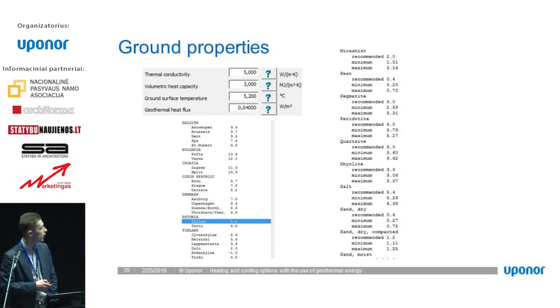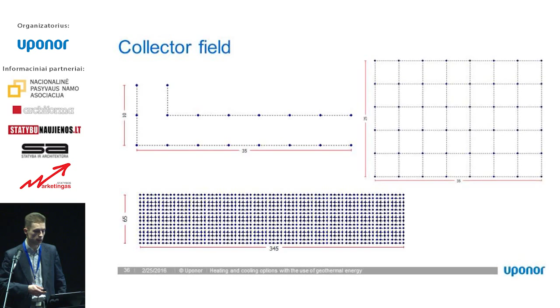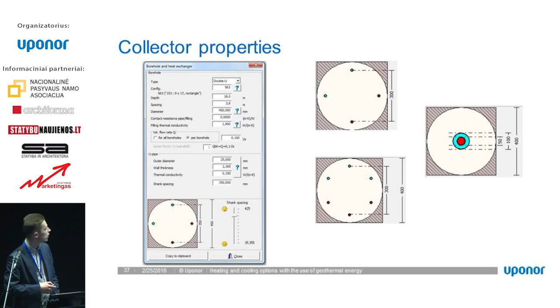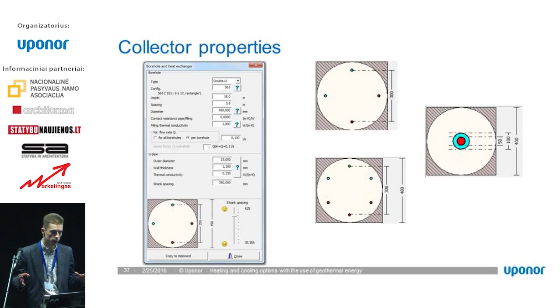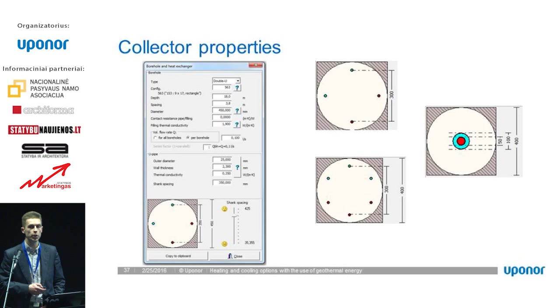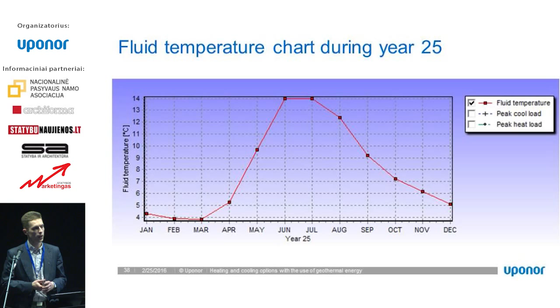Collector field - how the piles will be placed in the ground, what is the distance between them, how the pipes will be installed in the pile, what diameter to use - these are the things we put into the calculation software. Then we can see the expected temperatures in the piles considering the loads, how much energy we should get from the ground, and adjust the loads to the piles we have. That means if there are tall buildings and not enough piles, we have to decrease the energy we expect from the ground and add district heating systems or chillers to cool or heat the buildings.